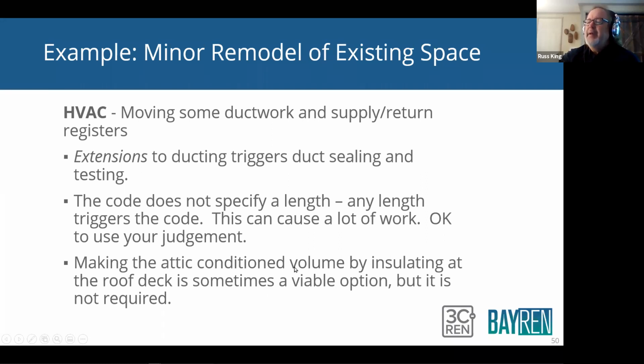Making the attic conditioned volume by insulating it at the roof deck, I mentioned this, is sometimes a viable option. I've actually seen that happen. I saw them do that at a Kelly Moore paint store sitting in the middle of a parking lot all by itself. They had insulation at the T-bar ceiling. All the ducts were above that. And they were doing a pretty substantial remodel and their energy bills were horrendous to keep this place cool. It was in Sacramento. And so what they decided to do, instead of insulating at the T-bar ceiling as part of this remodel, is they put new insulation at the roof deck and the walls above that.